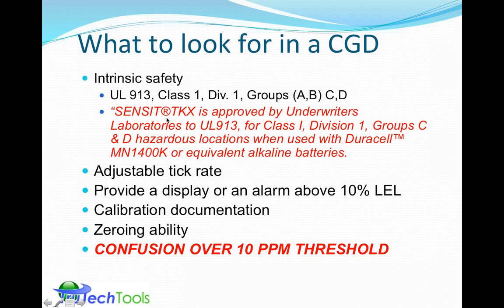There's also a little bit of confusion over the 10 ppm threshold. When people were originally reading the standard, going back to earlier this year, they had noted the 10 LEL, and then in some areas, I think it was actually New York State, they were looking at a threshold for the detectability of the gas at, I believe it was 20 parts per million. Well, most detectors are at 50 and a few are at 20. Then people read the 10% LEL and thought that had now dropped to 10 ppm threshold.